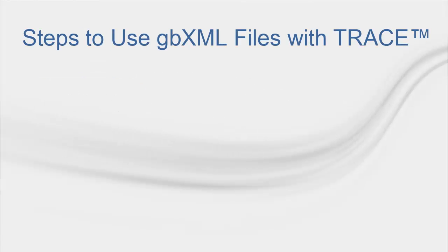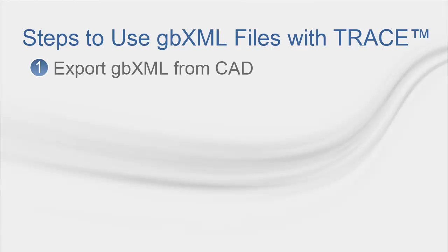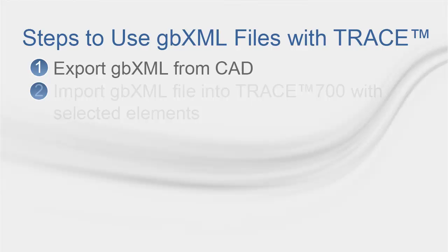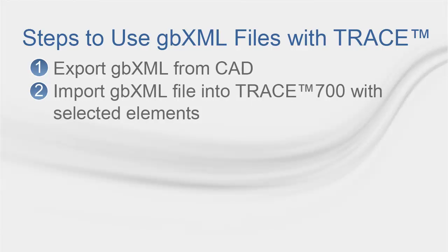Let's look at the steps needed to use a GBXML file in Trace. After the building has been created in the CAD program and it is ready for load analysis, export GBXML from CAD program. Make sure you save it with the name less than 28 characters and do not use any special characters on it. Number two, import the file into a new Trace 700 file. Select the elements that you want to import.